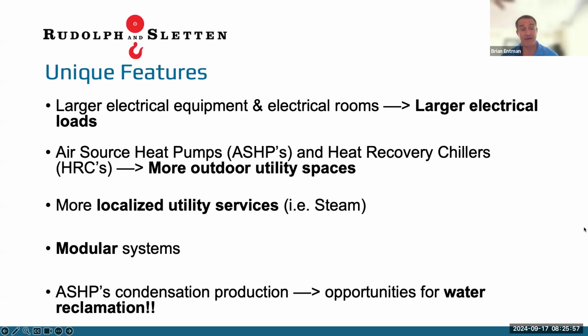Many of these systems are becoming modular, so we aren't seeing as many large centrifugal heat recovery chillers. Instead we see smaller modular scroll-type systems, multiple chillers in one package. The challenge is how many modules and how much you can achieve from one unit—these things are getting fairly sizable. Even at 300 tons, a modular heat recovery chiller is very long and takes up a lot of mechanical yard space, so while modularity helps, footprint still needs to be negotiated.